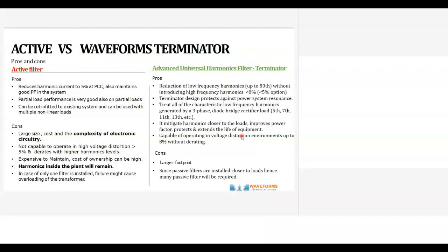With the advanced universal harmonic filter, the price is less. You can install it closer to the load. It reduces harmonics up to the 50th, so it performs much better than the active filter. Sometimes you can have other harmonics also, like the 25th, 27th, which is possible in some cases. Up to the 50th it can filter, and it doesn't introduce any high frequency harmonics. You can improve the performance by adding some windings to filter much better, so we can reduce it to less than 5% also.